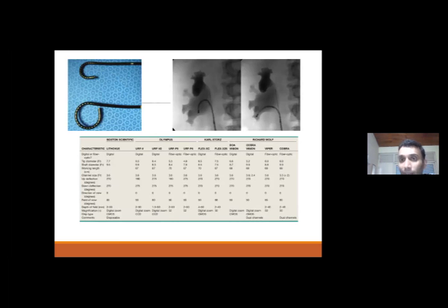border of the renal pelvis to create more secondary passive deflection. The Karl Storz, which created this, sometimes with a large wider pelvis, we can use the secondary passive deflection. Sometimes it can be difficult to enter into the lower calyx, so Karl Storz created a more exaggerated deflection of about 360 degrees.